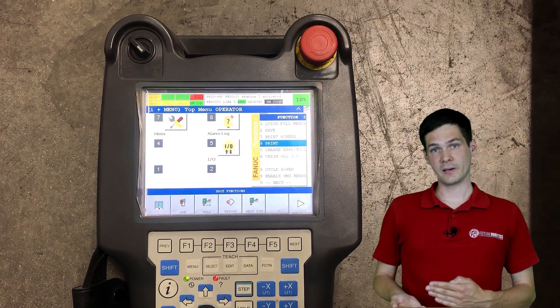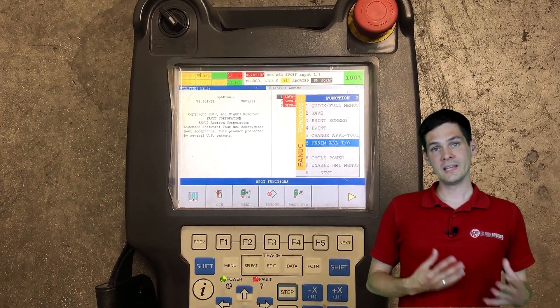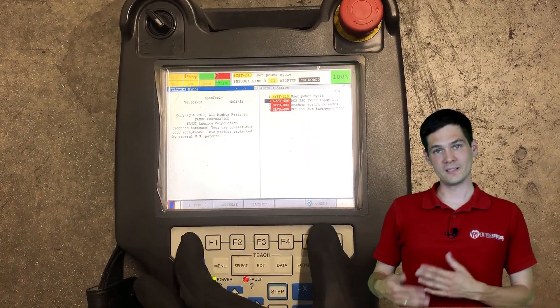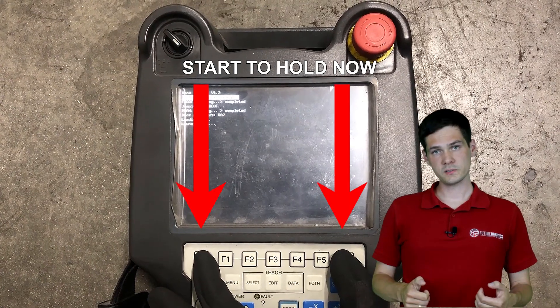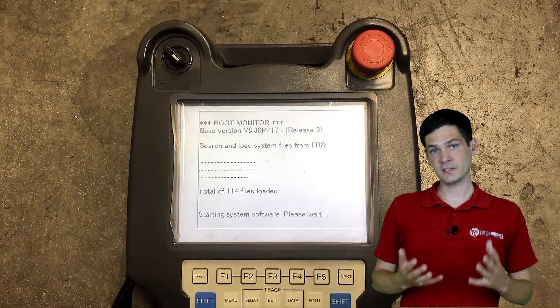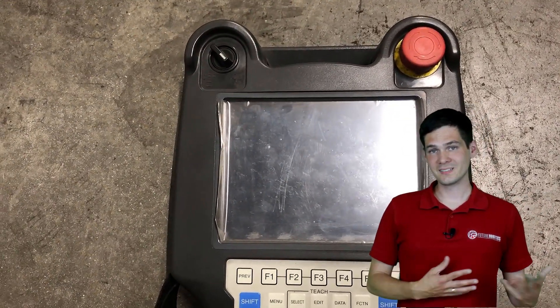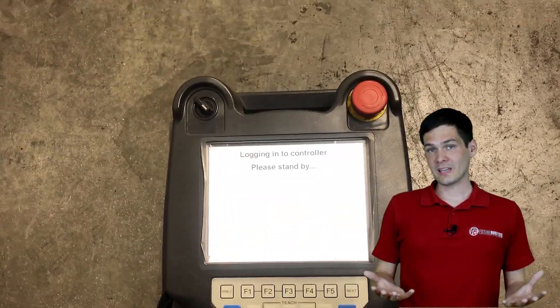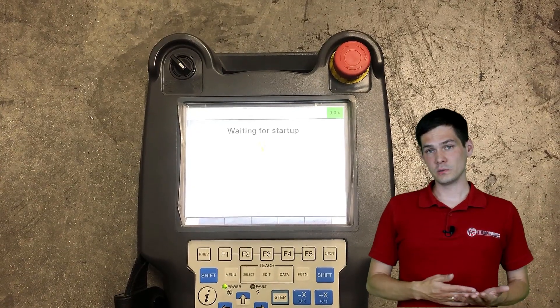You can do the cold start by going to the function menu and selecting cold start, or you can do it the old school way by holding the PREV and NEXT buttons while cycling power the controller. You can cycle power through the circuit breaker, flip it, turn it back on, and hold those two buttons. This type of restart is going to reinitialize the IOs and reinitialize the variables that maybe got stuck or are in an unknown state — that's why the robot is acting weird. It won't break anything; you can do it in most cases. If the robot won't start the PNS or the style and you don't know what's going on, just do the cold start. It should solve the issue in 99% of cases.